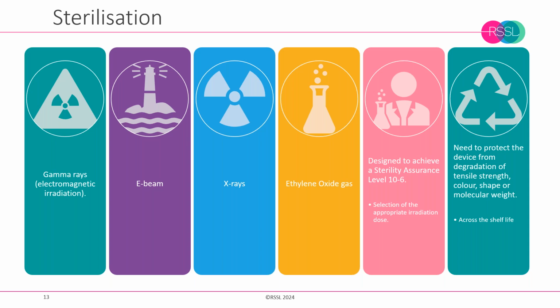Gamma is also fairly good at avoiding material degradation. And by degradation, this is something that we'll return to, but it is an important factor. You know, it might be perfectly feasible to sterilize something, and it may or may not degrade, or there might be degradation over time as we move towards the end of the shelf life. So we're talking about changes to the properties of the polymer. We might see an alteration of tensile strength. We might see a change in color. So some of these processes can render transparent or translucent plastics and turn them yellowish in color. We could get alterations to shape or molecular weight.